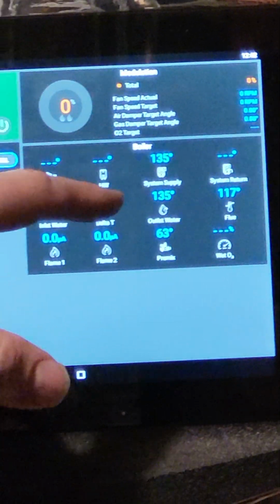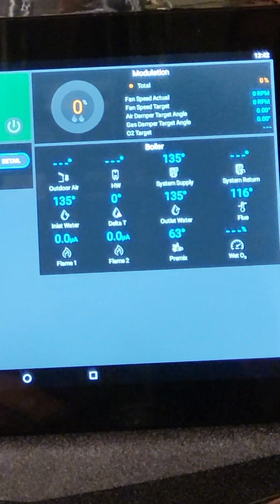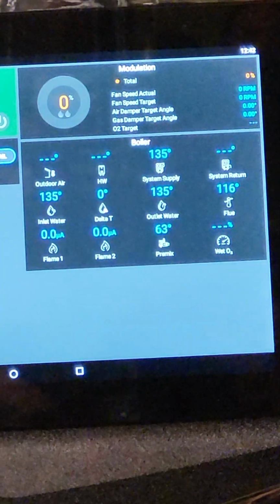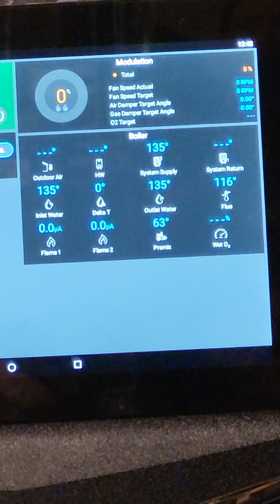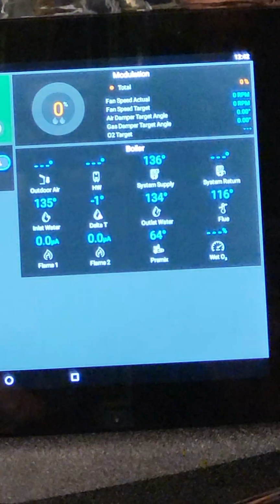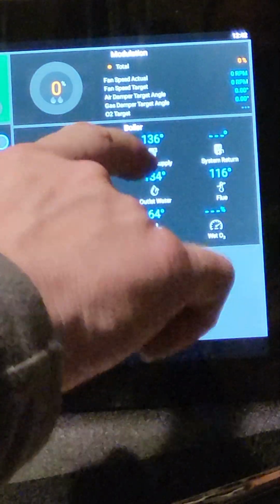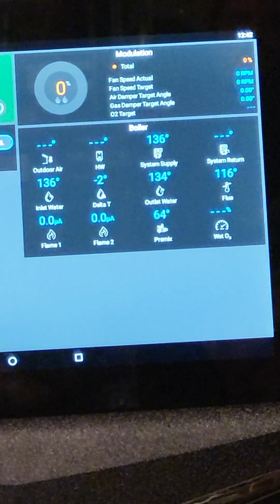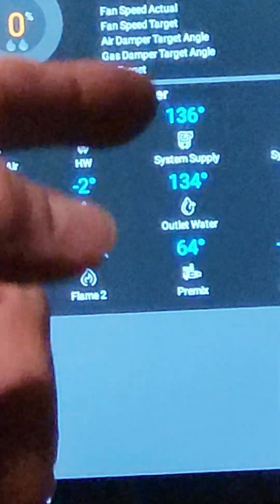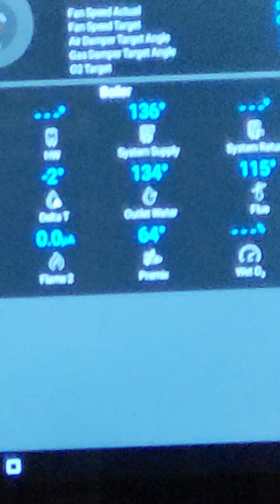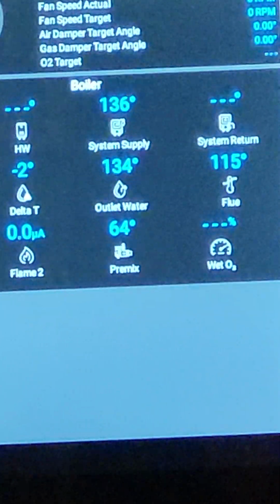So on the boiler area over here, you can see outdoor air is not hooked up because the control contractor has their outdoor sensor. Kind of silly for us to have one when they're making the reset. HW is hot water. We're not doing domestic hot water, so there's no sensor hooked up. System supply is hooked up. That's the sensor we were talking about up there. That's reading 136 right now. System return is blank because we don't have a system return sensor.